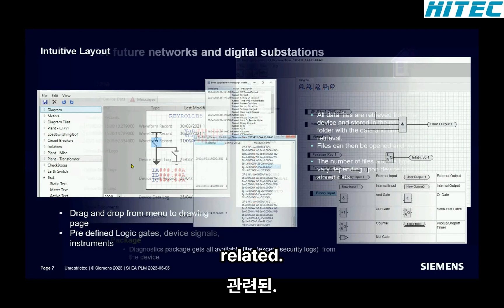When you get the device data from an online connected Reyrolle 5 device, you can access all waveform records, device event logs, fault logs, and other logs. You can double click on them, which will open in a pop-up window, and they will sort from the most recent one at the top to the older ones lower down.